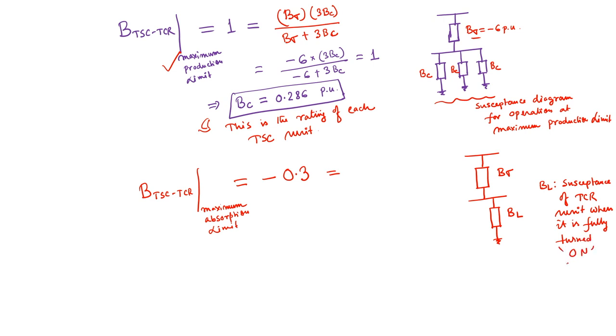This is something you need to understand, because this is representing a variable susceptance, but we consider the extreme operating condition, that is maximum absorption limit. At that condition, the susceptance of the TCR would be the maximum susceptance that it can provide, corresponding to the TCR unit being fully turned on.